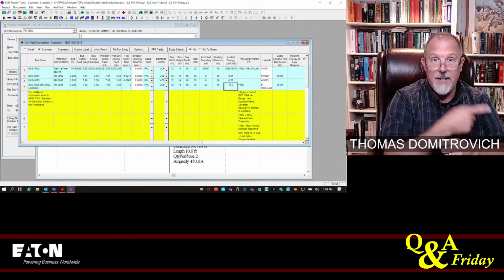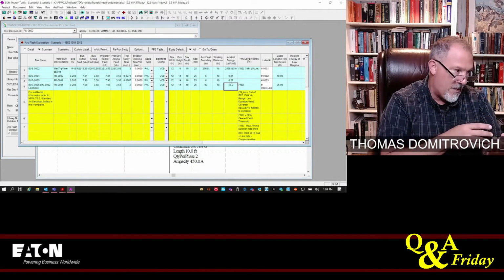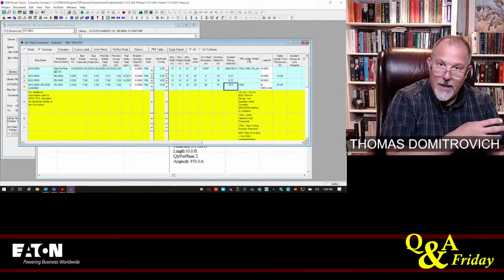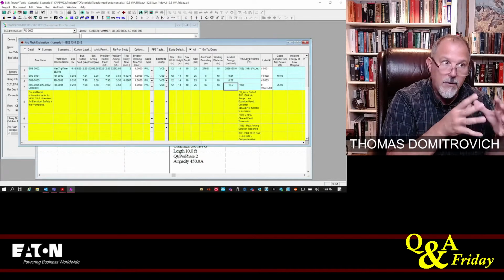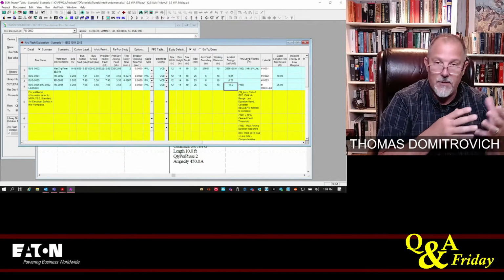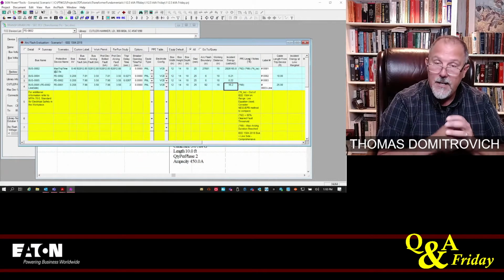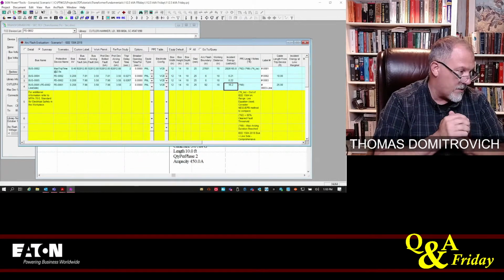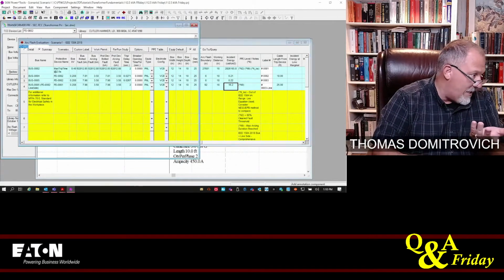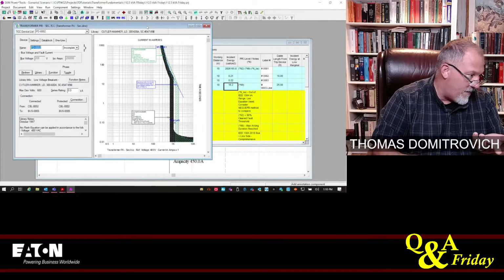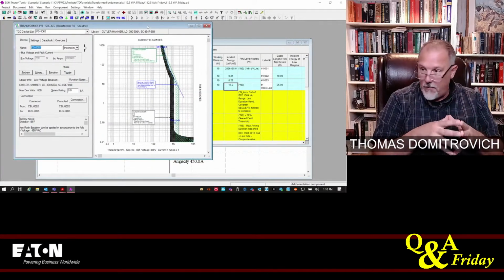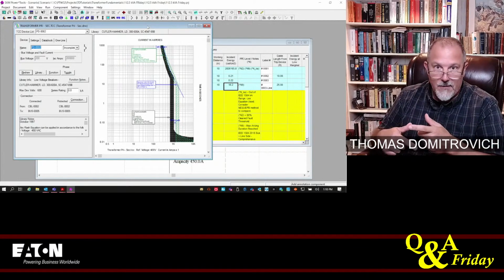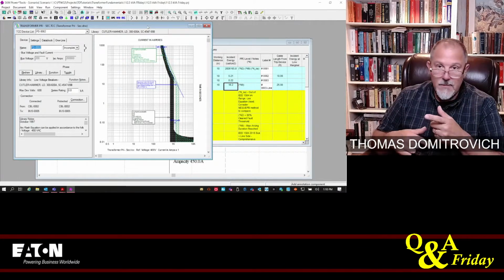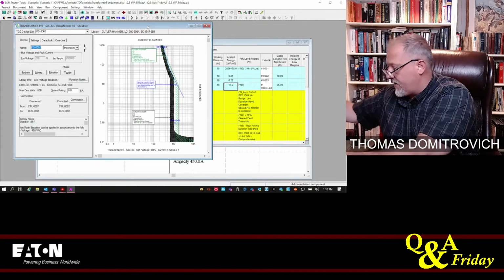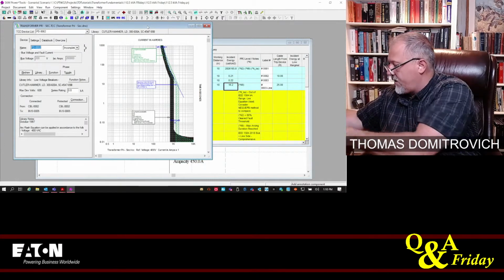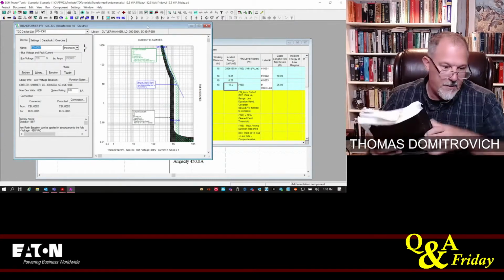Now, the incident energy, obviously, in that transformer or in this breaker in a box or a fusible disconnect is going to be higher, but the likelihood of having to get in that panel board is low. So that's what we did. So we did a 112.5 kVA transformer. We picked the primary and secondary overcurrent devices, and now let's do the code references.